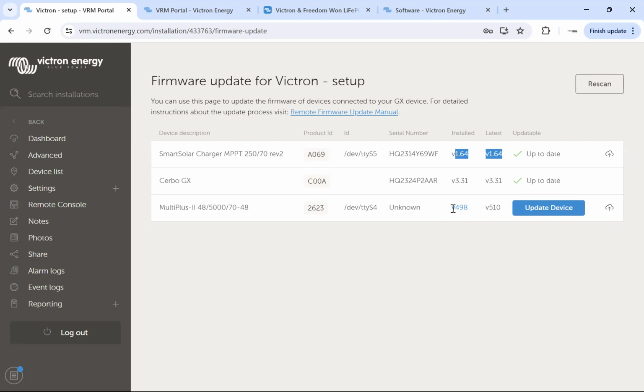Once you've pushed that update into the inverter, it's going to download the old software settings from the inverter and ask you to migrate the settings, meaning it will change the downloaded software settings into an updated file that suits the latest firmware you've just updated in the inverter. You then need to go through those settings and upload that back into the inverter - we'll do that right now. The firmware update on an inverter is by far the most risky and comprehensive firmware update you're going to do on a Victron system.